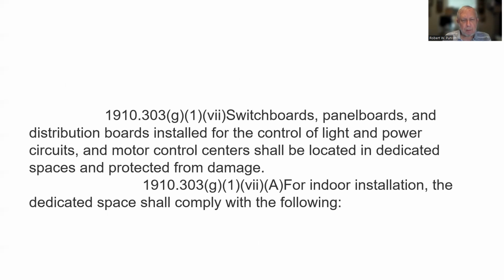Switchboards, panel boards, and distribution boards installed for the control of light and power circuits and motor control centers shall be located in dedicated spaces and protected from damage. They had these in a lot of the food facilities. They had special electrical rooms for this type of stuff, and they were secure. For indoor installation, the dedicated space shall comply with the following.